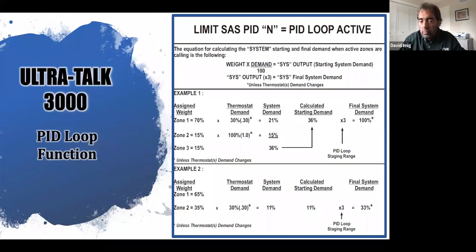If I'm within 1 or 2 degrees and maintaining that, you're going to get a 30% demand. If I fall below that, you could possibly get to a 60% demand. And if I'm going into a setback, a deep setback, or a semi-deep setback, you could see the demand of 75% or 100%. I need to recover 6, 8, 10 degrees. So you're going to get more of a demand. What I do in this case as part of the formula is I take the demand times the weight, and that gives me a starting point of 21%. That means I'm going to start my system up, my equipment up, with a demand of 21%, not with a firing rate of 21%, but with a demand of 21%.